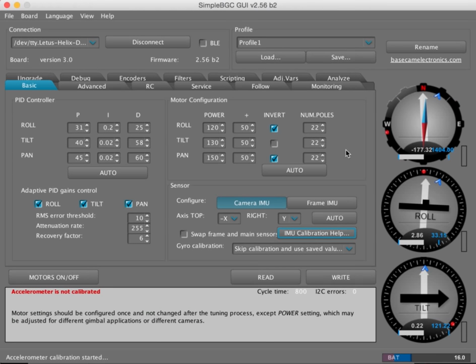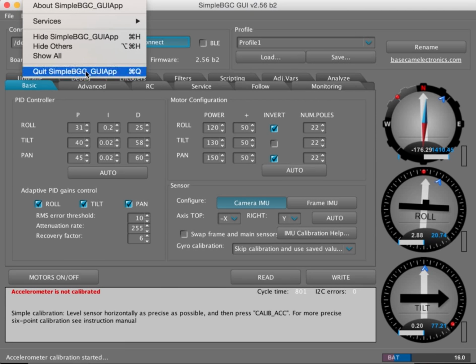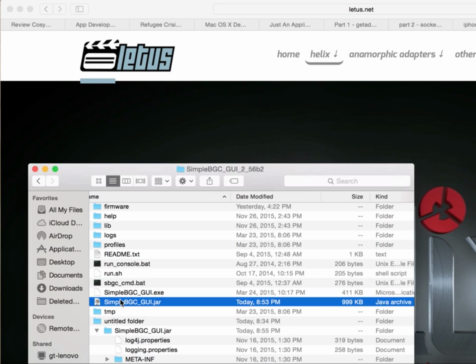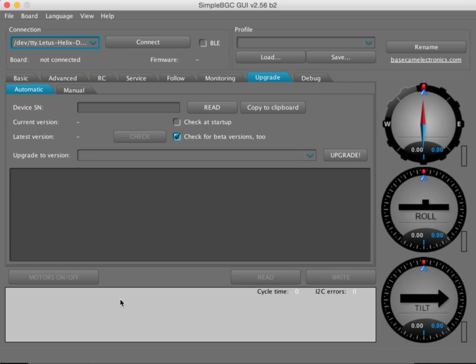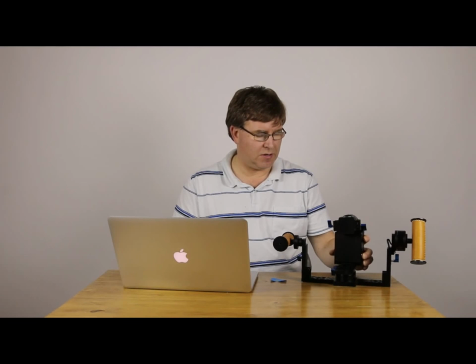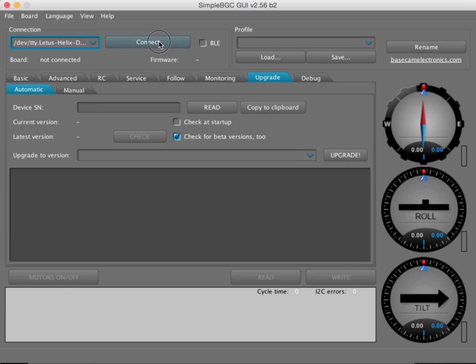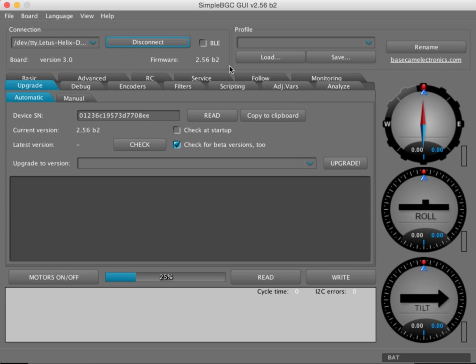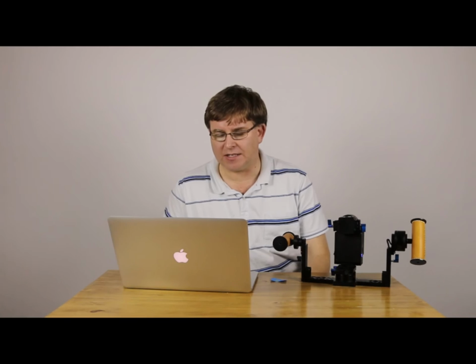Now, one of the things I have noticed about this version of the firmware is it doesn't always get rid of this message down here, that the accelerometer is not calibrated. So what you may need to do here is actually just go ahead and quit the GUI, and if you come back in, I think that you'll find that it is actually going to go ahead and shut this off, and then I'll turn it back on, and we'll turn off the motor with one click of the menu button. Since I'm using Bluetooth, I'll select this one, connect. This is actually a little slow in connecting. Normally it only takes a second or two, instead of 3 or 4. Okay, and now you'll notice here that the accelerometer not calibrated box is gone.